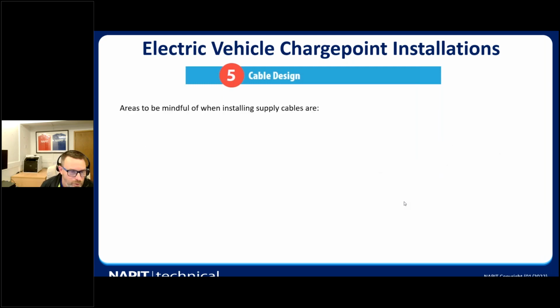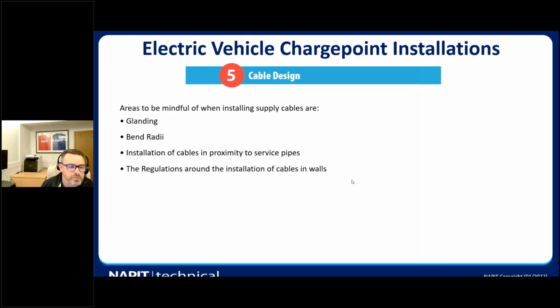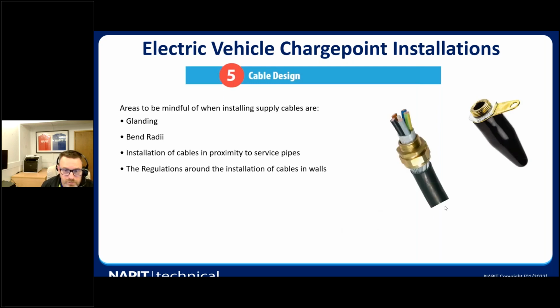And areas to be mindful of when we're installing supply cables are the glanding, which is important. It's correctly glanded to stop ingress in there. The bending radius of the cable, the installation of cables near service pipes to make sure they're not too close to them, where it can cause damage or problems with them, and the regulations around installing cables in walls. So, just an example of some cables in there.